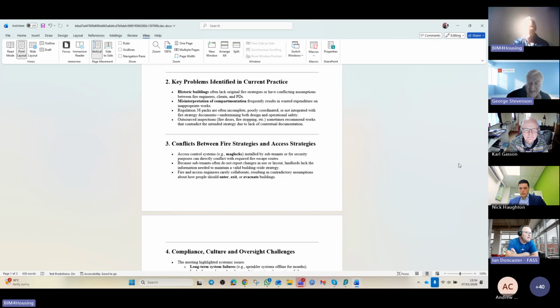There you go. Yeah, one thing we often see from the smoke ventilation side of things is where people doing access control have no idea about anything other than access control, and we often get people coming to service an access system and they disconnect things and they don't understand what the whole system does.